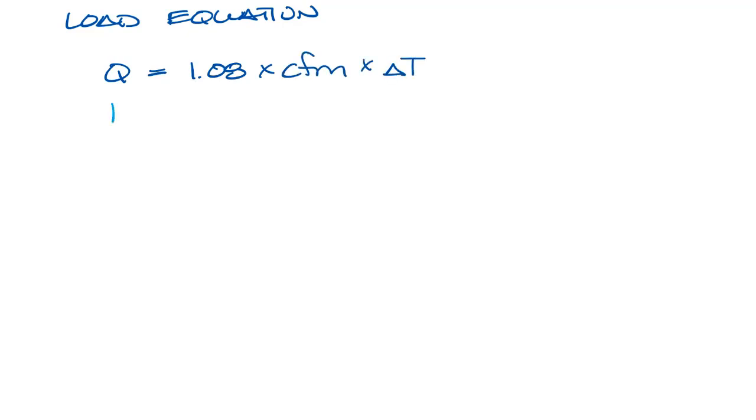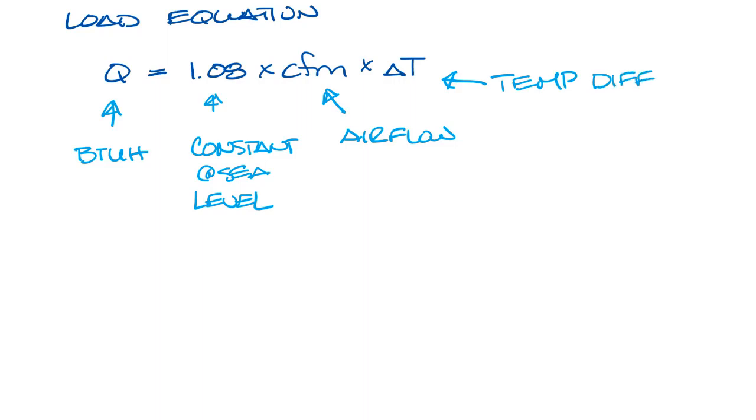Q is measured in BTU per hour. 1.08 is a constant at sea level. CFM is your air flow. And delta T is the temperature differential between the temperature you're putting into the space and the temperature you want to maintain in the space.